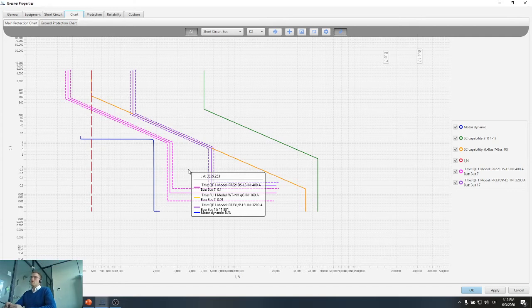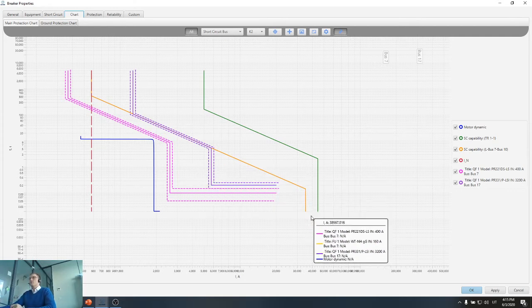So all you need to do is block the numerical relay operation during energizing, and you need the second harmonic measurement for that. But even in this case, it's not that important, because in some markets I know that the transformer is energized in several ways. You just connect the circuit breaker, the transformer will charge a little bit, the breaker will disconnect, then you connect the breaker one more time, and after several times you are capable of energizing the transformer. Of course, if the transformer is very big, it's also possible to use a generator to charge the transformer, and then when you connect to the network, the inrush current will be very small. So there are very different ways to connect the transformer, and maybe again during today's training, because these are only 2 hour trainings, I will not cover all of them.